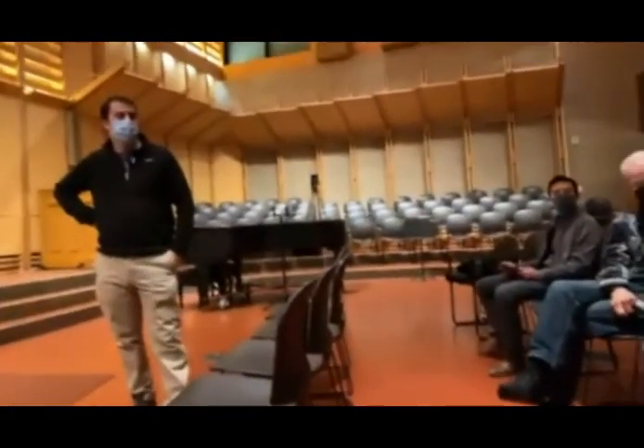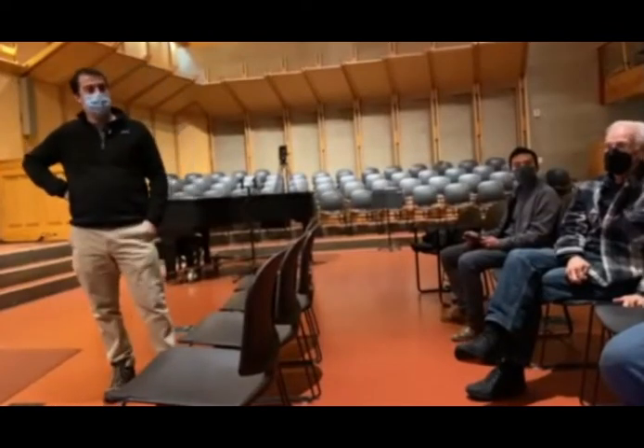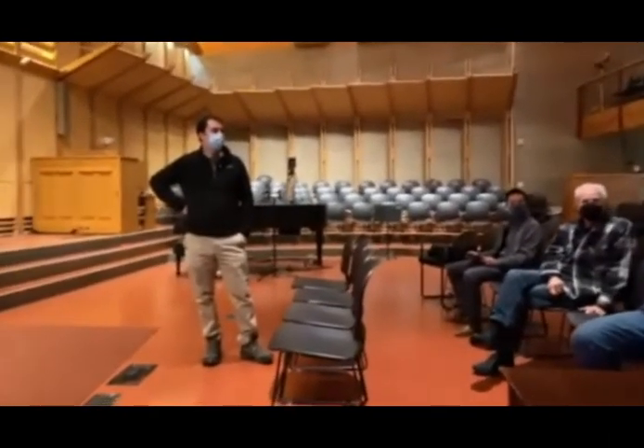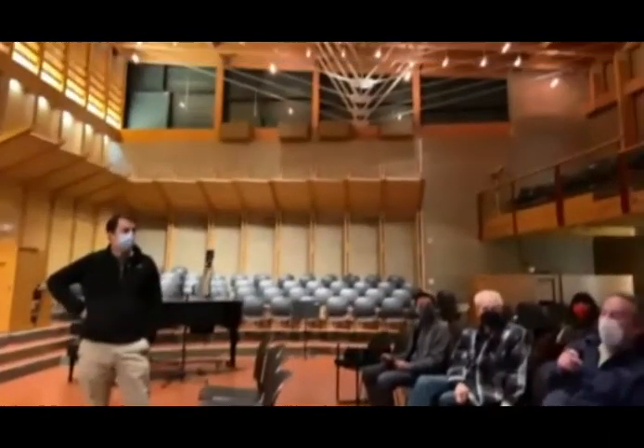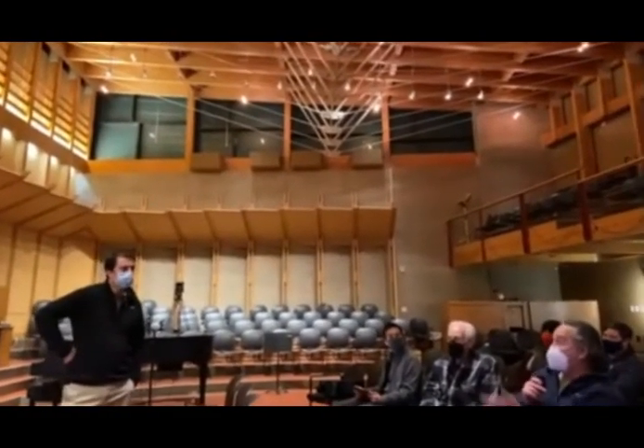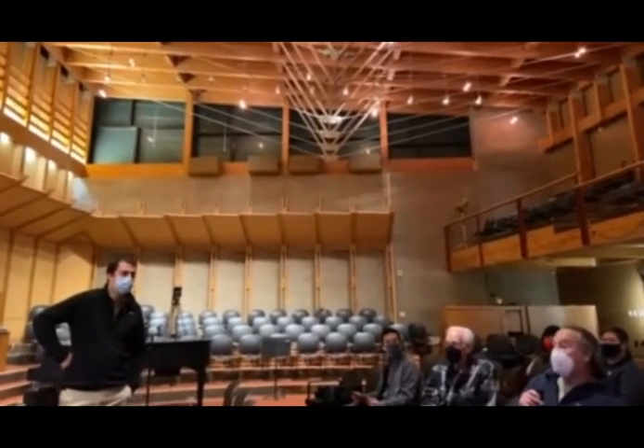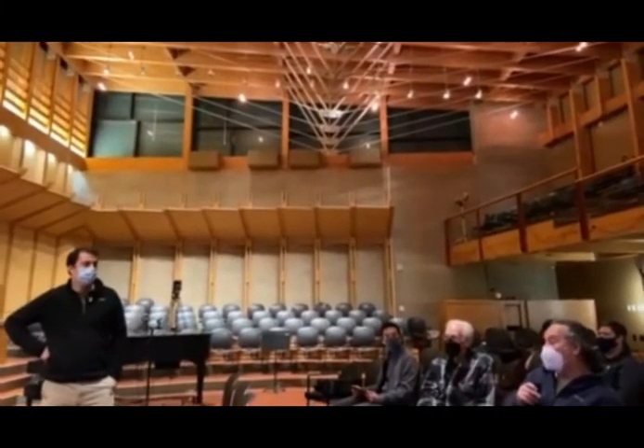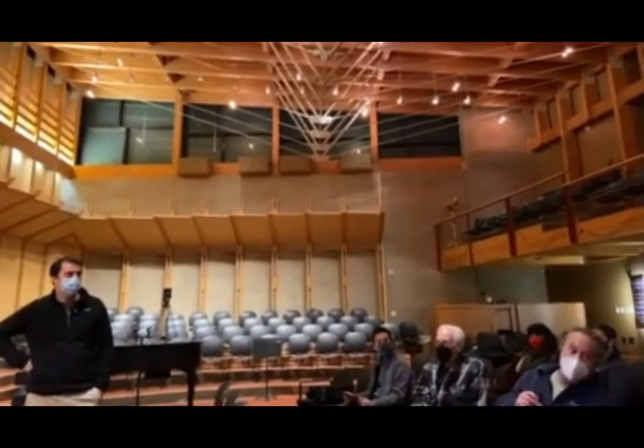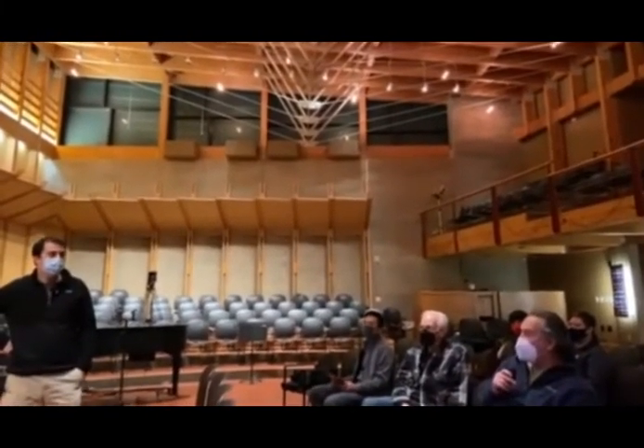Back in the classrooms, half of the classrooms were 1989 construction, and the other half is the 2009 construction. Between those two, that makes up a zone, and that zone has been challenging to keep comfortable. If you asked those people, it would really depend on which classroom you were in. If you were in classroom D or E, you probably were cold, or if I adjusted it, you might be hot. And all that adjusting I had to do manually with the damper, so there were no automatic controls with that.